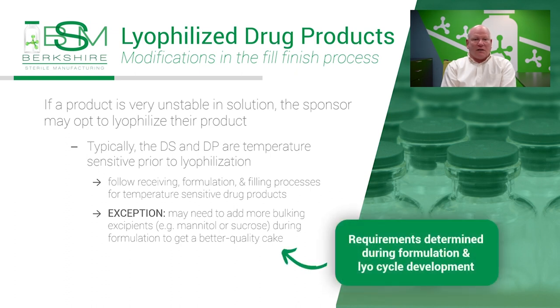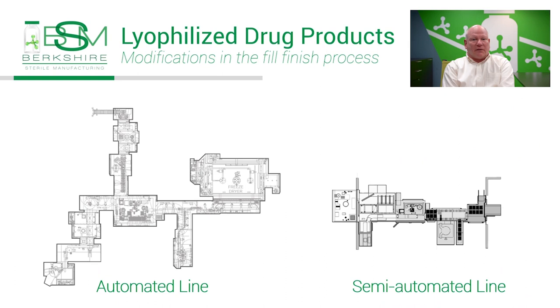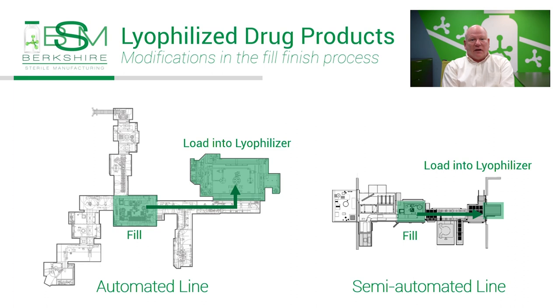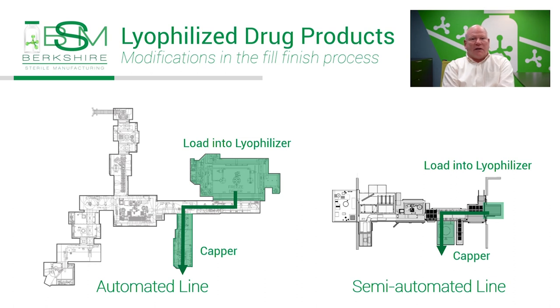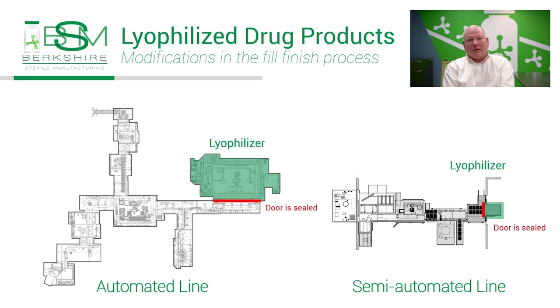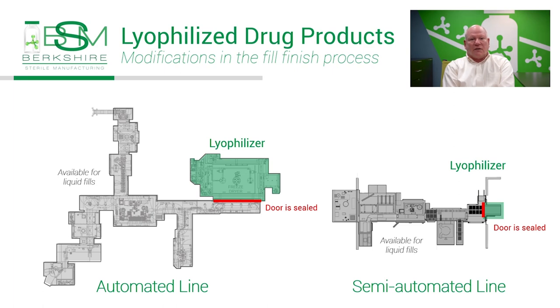In formulation for lyophilized products, we typically add bulking excipients like mannitol or sucrose to get a better quality cake in lyophilization. These requirements can be determined during the lyo cycle development, which is a service we offer at BSM. There's not too much that's unique to filling lyophilized drug product other than the added step of directing the filled vials to the lyophilizer and then out once the cycle has been completed. Our semi-automated and automated filling lines are equipped with isolator-based lyophilizers.